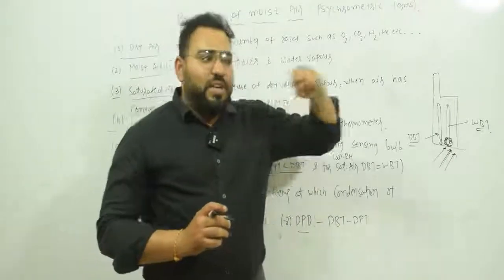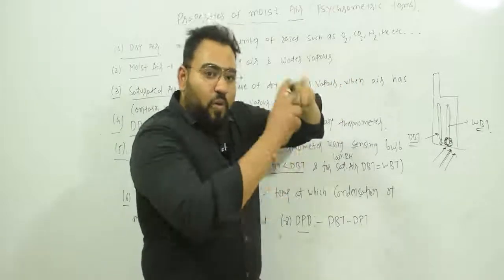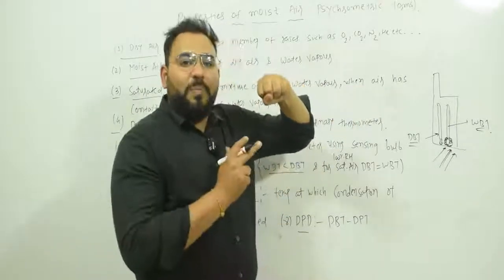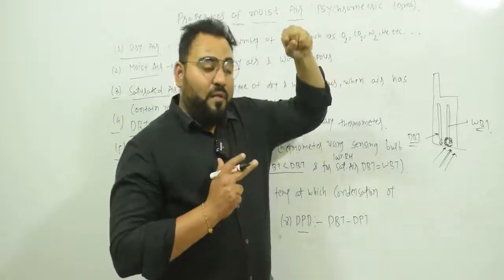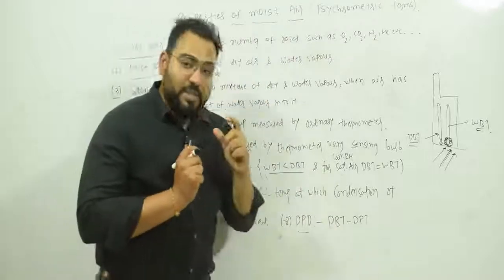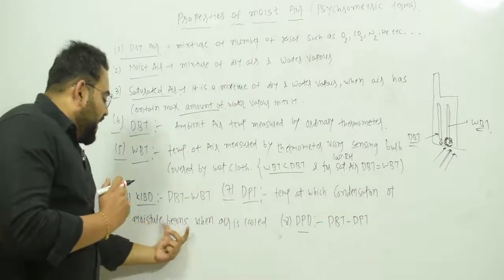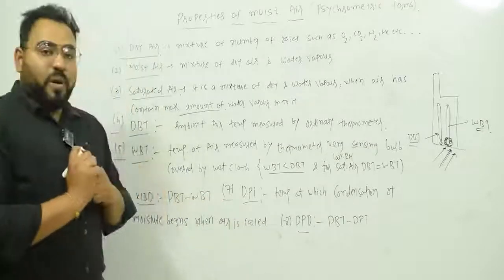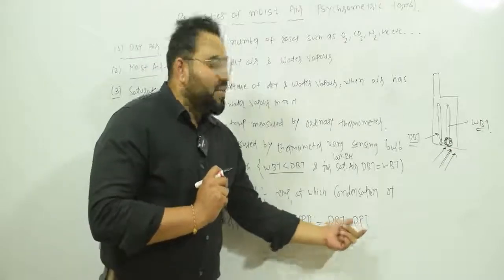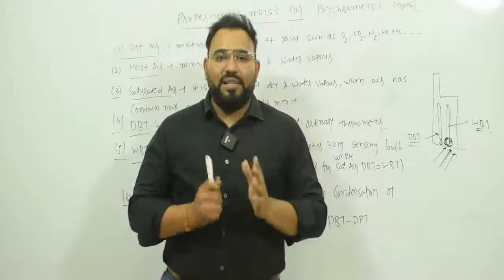At the dew point, the air is at maximum water vapor capacity. If you cool it further, the capacity to hold water vapor is reduced, so some water vapor condenses and falls down in the form of dew. That is why it is called dew point temperature — it is the temperature at which condensation begins when air is cooled. Dew point depression (DPD) is defined as dry bulb temperature minus dew point temperature. The remaining psychrometric terms will be covered in the next video.